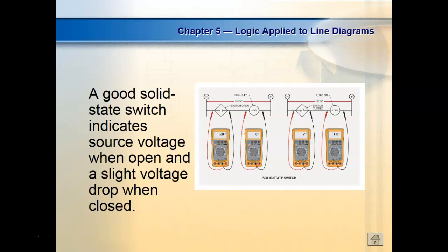In low-power circuits, these solid-state sensors are what we call three-wire sensors. We literally hook them up across the line because on a 24-volt circuit you can't afford to drop 6 volts. We'll show you some of these when we get into the sensor section. The sensor we're going to use is called an inductive sensor — it's a two-wire sensor, works off 120 volts. If you measure across it when it's simulating a closed contact, you're going to measure about 4 to 6 volts.